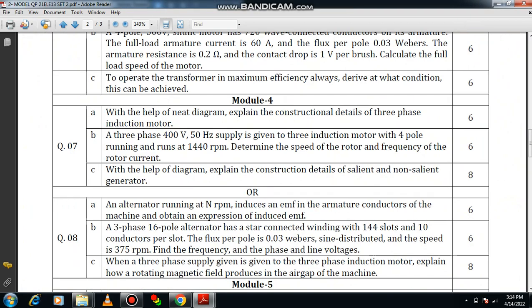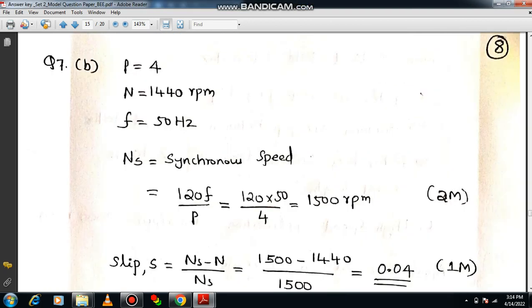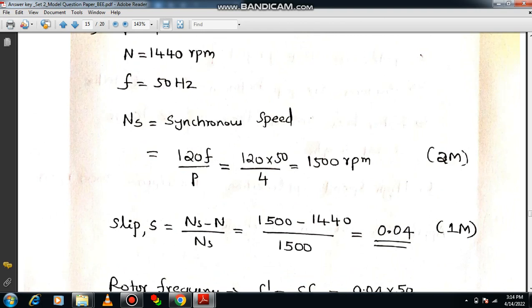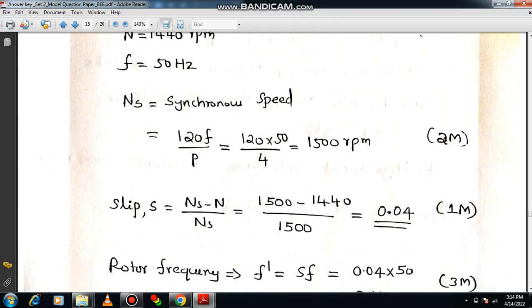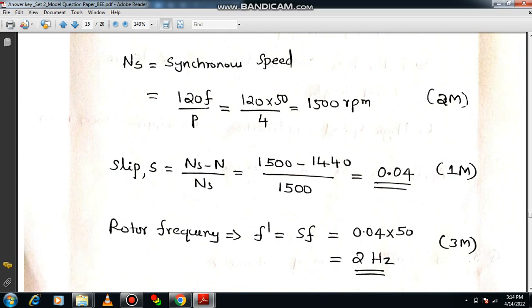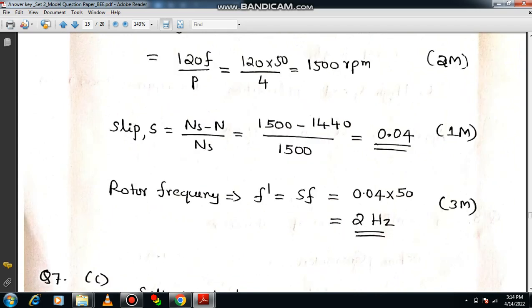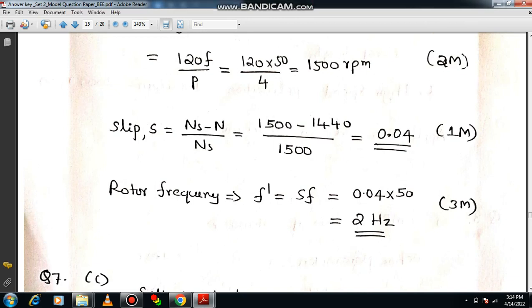Numerical example: a three-phase, 400 volt, 50 Hz supply is given to a three-phase induction motor with four poles running at 1440 rpm. Determine the speed of the rotor and frequency of rotor current. Given: P=4, N=1440 rpm, f=50 Hz. Synchronous speed Ns = 120f/P = 1500 rpm. Slip s = (Ns − N)/Ns = 0.04. Rotor frequency f' = s × f = 0.04 × 50 = 2 Hz.